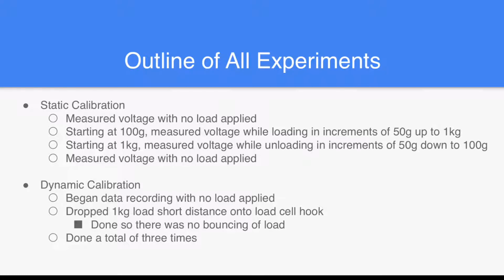For the dynamic calibration, we began to record data with no load applied, and then we dropped a 1 kilogram load a very short distance onto the load cell hook, and this was done so that there wasn't any bouncing of the mass to skew the results. And this was done a total of 3 times.